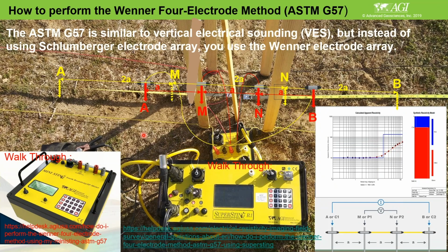Okay, how do you perform this four-electrode ASTM G57 measurement? As I said, this is a typical vertical electrical sounding. You just need to do vertical electrical sounding, but instead of doing Schlumberger, which we are most familiar with and do easily, now you need to do it with the Wenner electrode array. That's what the standard requires.